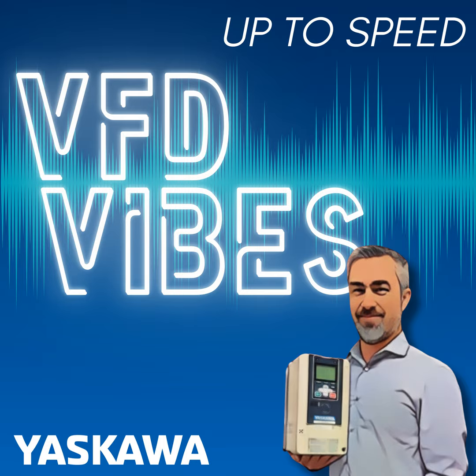One of the things is, we put all these service conditions in the manual. Our drive will run with a 2% imbalance. It'll run at full load. We have all these things we say, and by the way, you can be at 40 degrees Celsius while all this is going on. Yeah, that is true. But if you want to run that drive for 20 years, if you want to extend the life, you don't want to do all those things at the same time. And especially if you're going to push things a little bit in one direction, you want to kind of push back.